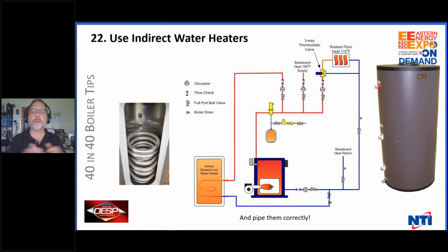I went on vacation, turned my boiler off so that my tank couldn't run, came on, turned the switch on 2 weeks later, and my boiler didn't come on. Not because it was busted, but because I didn't need heat until the first kid got a shower, and then it ran. They're amazing. Save a ton of energy and give an immense amount of hot water, and you don't have to worry about hard water. You just run it through it. If you have water that's very corrosive, be careful of what you use, and you might want to think about installing electric anode rods on indirect water heaters. Most do come with a lifetime warranty, and it is limited, meaning you go through 3 or 4 tanks and they're going to come back to you and start wanting water samples.